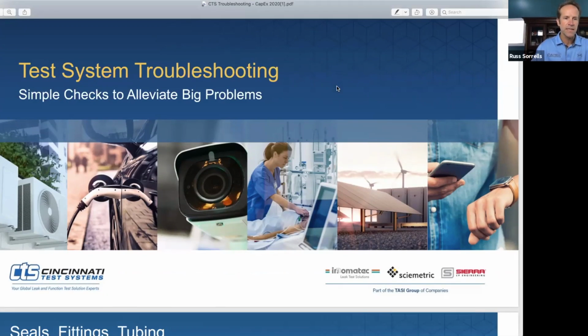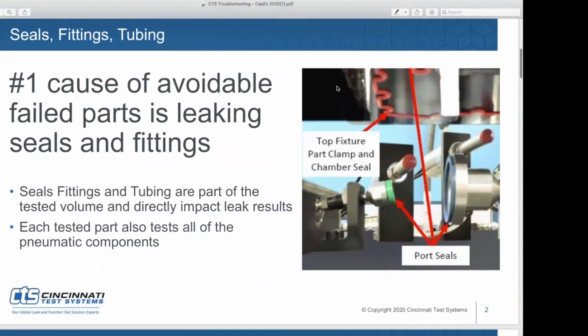Let's talk about troubleshooting leak test equipment. Oh yeah, so the biggest thing, seals. If you can't seal a part, you'll never be able to leak test it. And we find those are the biggest causes of problems for leak testing. Seals that are not compressing evenly on a large surface area. So you can see in this picture, there's a large flat cut seal. And if that doesn't come into a part as flat as possible to the surface it's going to contact, and it's got a slight angle to it, you could end up burping through that seal during test.